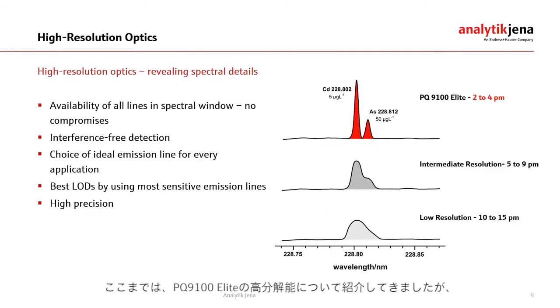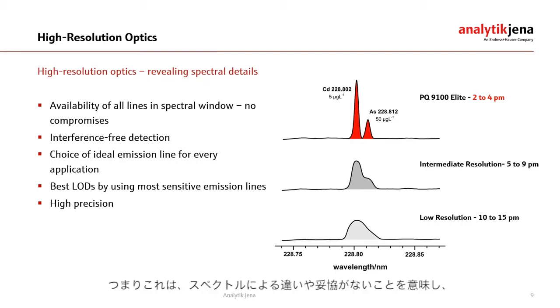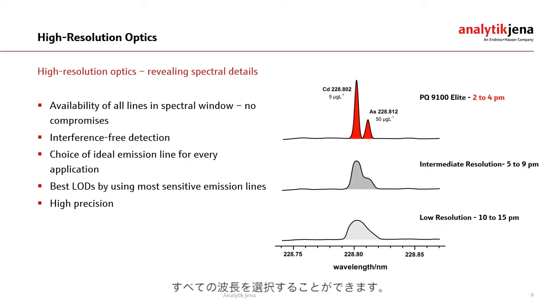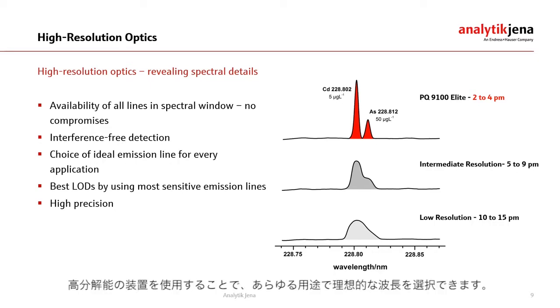Since I have introduced the PlasmaQuant 9100 Elite as a high resolution ICP-OES, we cannot close this webinar without talking about the main feature of the instrument. But how does high resolution improve your specific analysis? First of all, our instruments provide complete spectral coverage from 160 to 900 nanometers — no spectral gaps, no compromises. This allows for the selection of every analytical line for each element. And when your favorite emission line is interfered, this is where high resolution comes into play, making it possible to choose the ideal emission line for every application.